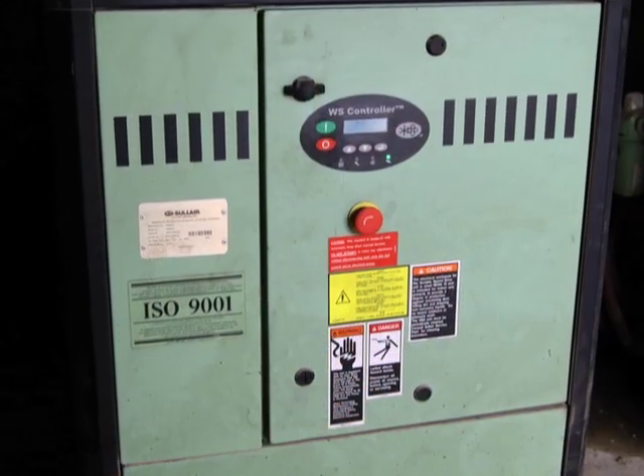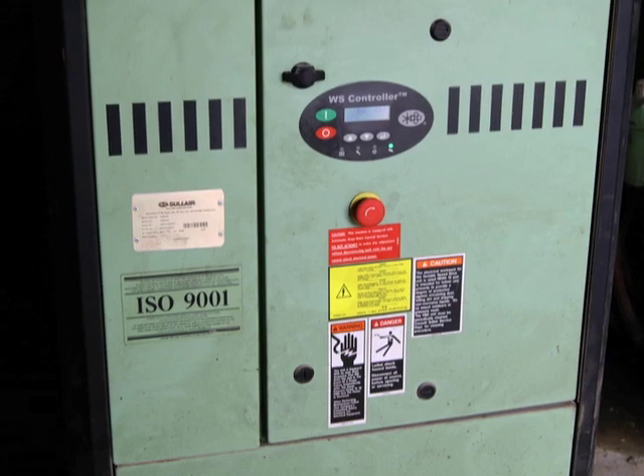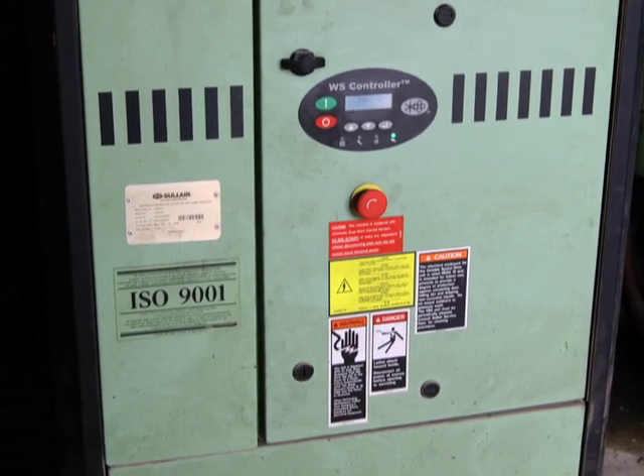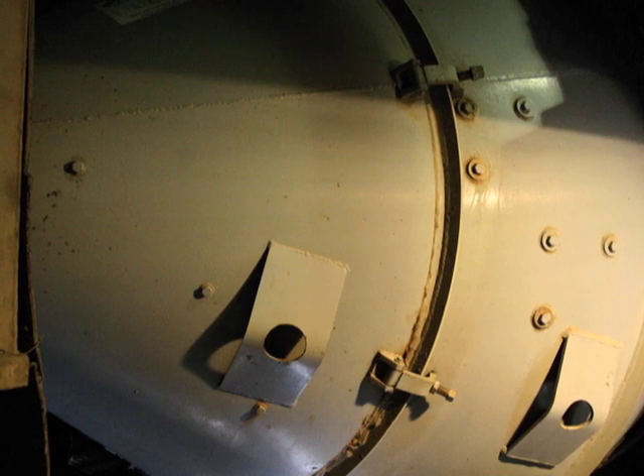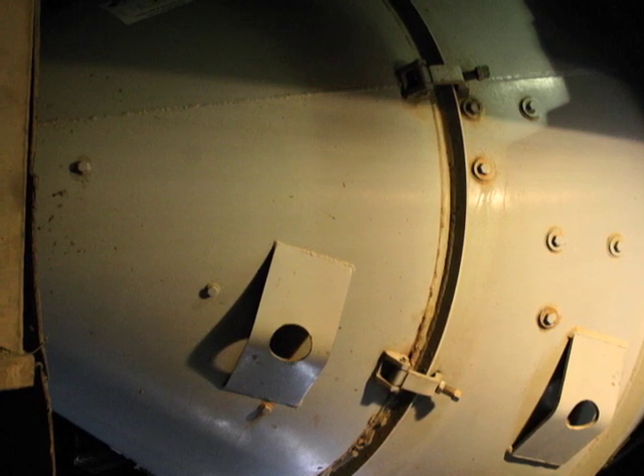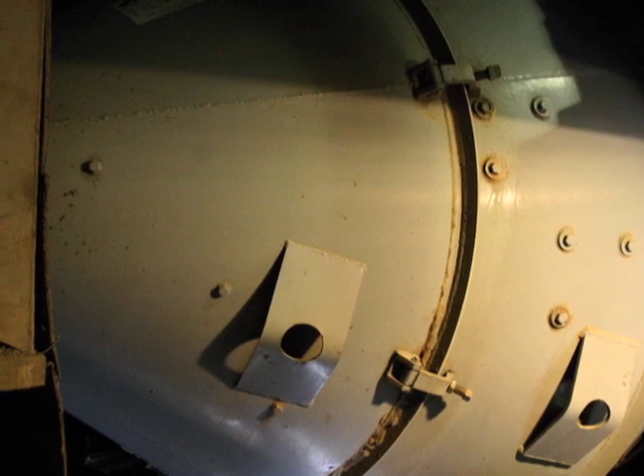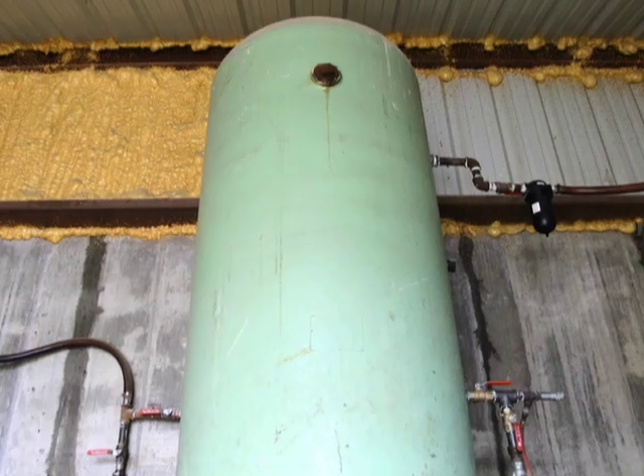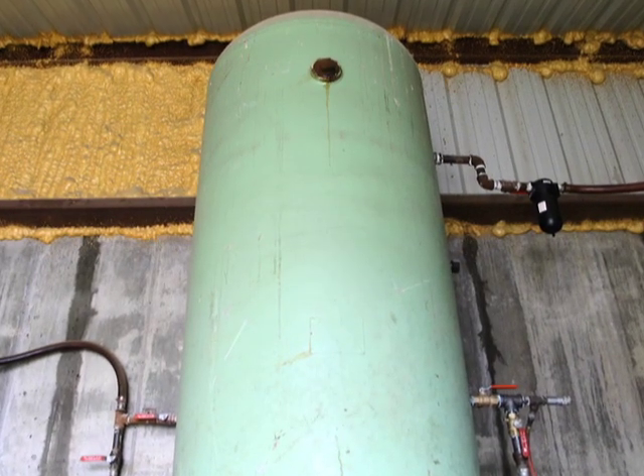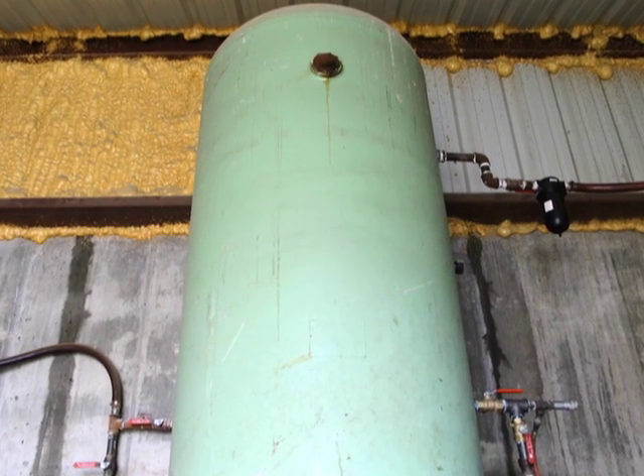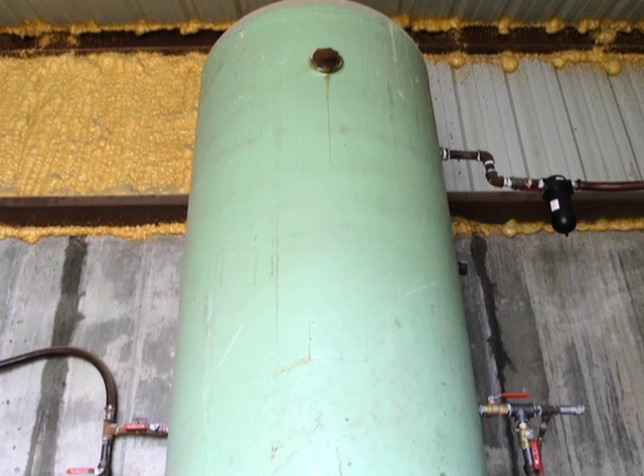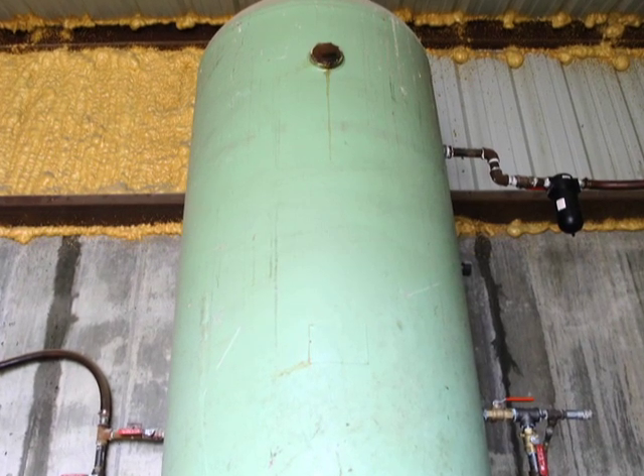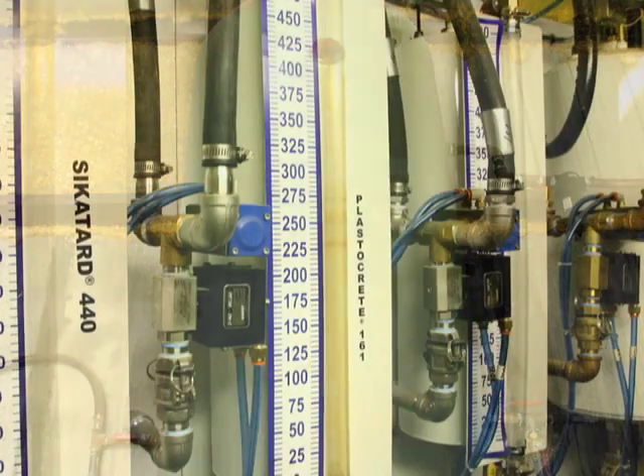Pneumatic energy is actually an air source of energy found in air compressors like this one. Gravity is a form of energy present in the operation of a central mixer at the plant. The mixer can be locked out, tagged out, and tried out in the up or in the down position. Stored energy can be present in forms such as spring, air, hydraulic, or chemical. Air compressors are likely users of stored energy.